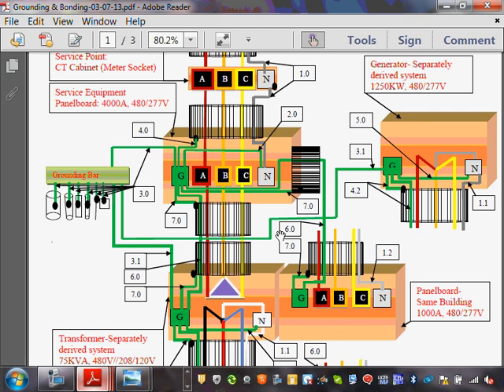If it's a regular system, it's already referenced to the ground. It doesn't matter; you pull the neutral if you need it. But if it's a separately derived system, take this piece here out, and now this neutral has to be tied to the ground. How are you going to tie it to the ground? You're not tying it here, so you have to pull it all the way and tie it right here, which in turn references it to the ground, regardless of whether you need it or not, because you need to bond it. Any comments, guys? Any questions?